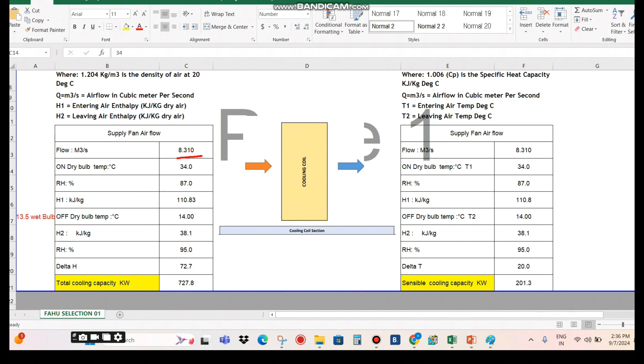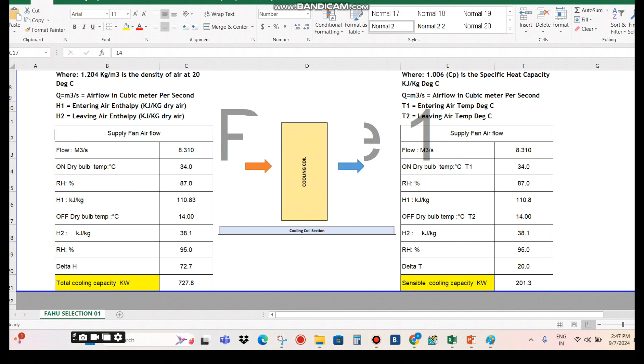Continuing in the Excel file — the flow is 8,310 liters per second for the high-rise building, so 8,310 divided by 1,000 gives 8.310 m³/s. The on-coil dry bulb temperature is 34°C and wet bulb is 32°C, which is the monsoon/worst country condition. The corresponding RH is 86.9% (rounded to 87%) and the on-coil enthalpy is 110.826 kJ/kg. I have entered all these values — on-coil dry bulb, wet bulb, RH, and enthalpy — into the Excel file.